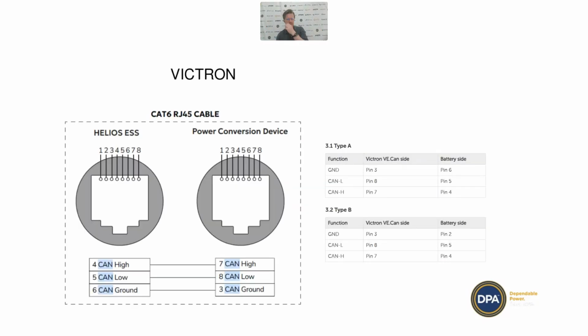So Helios commissioning with Victron. Like I've said, the pinout is different on Victron as to what you have on most other equipment. So the pinout on the Helios is pins 4 and 5, but the pinout on the Victron is pins 7 and 8. So you just want to buy the type A cable when you buy the system, and that translates it from one to the other.